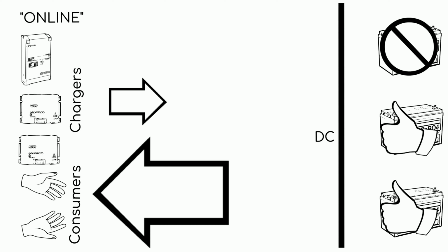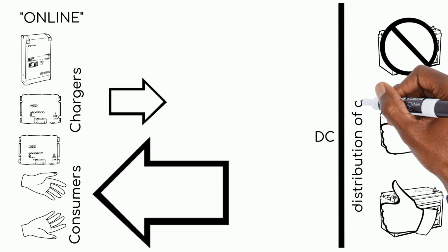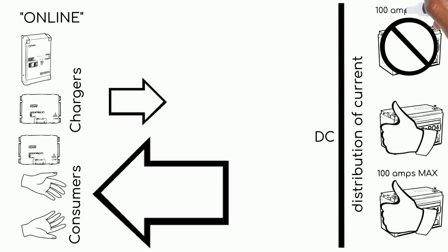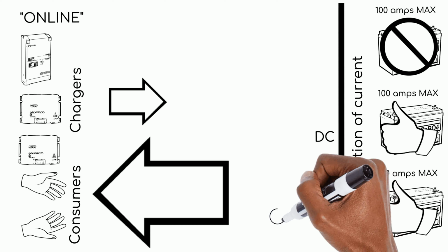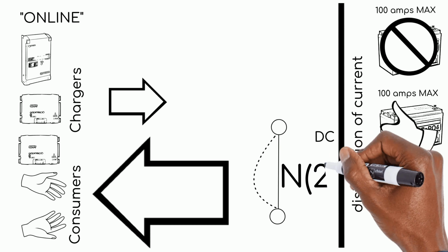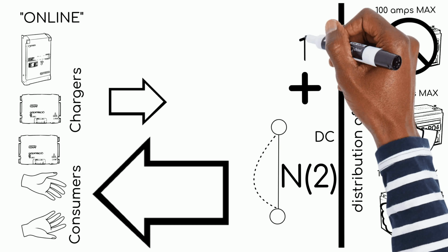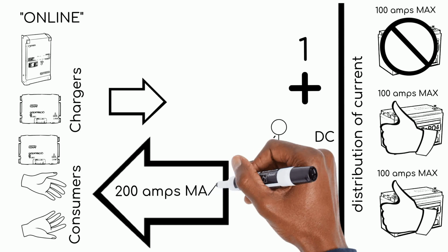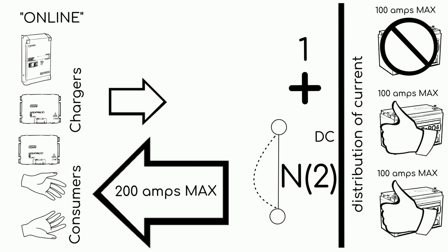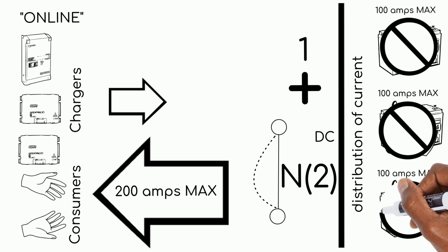But when creating such a system, you must think about the correct distribution of current within an electricity storage network consisting of parallel batteries. In addition, since the fault tolerance of a battery consisting of multiple sets of cells is organized through redundancy n+1, the maximum current in the system should not exceed the maximum current for n batteries. Otherwise, the failure of one battery will inevitably lead to the death of the others.